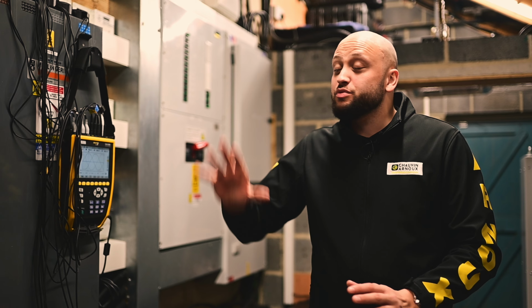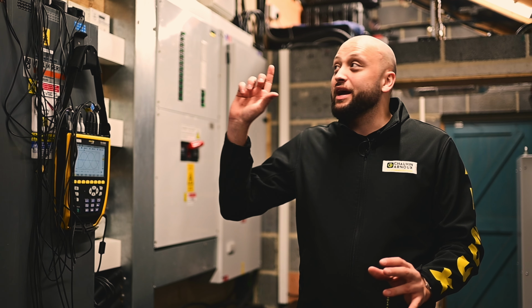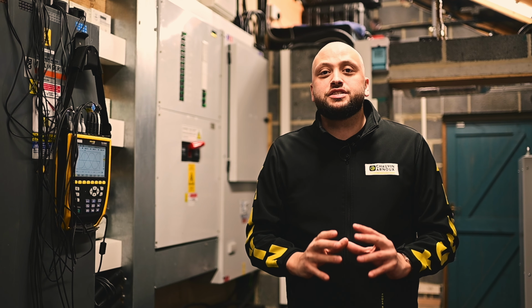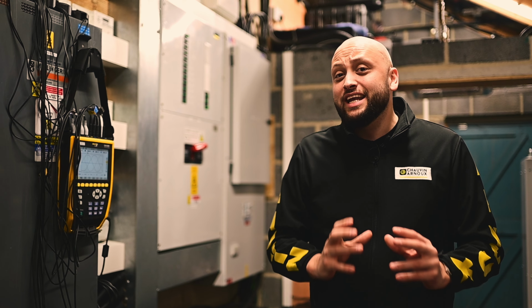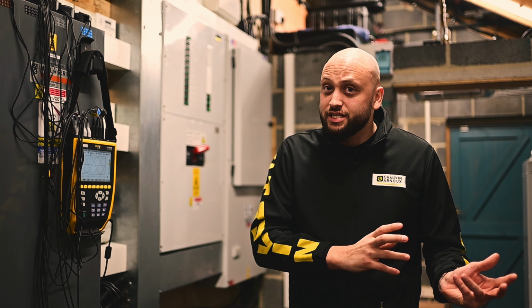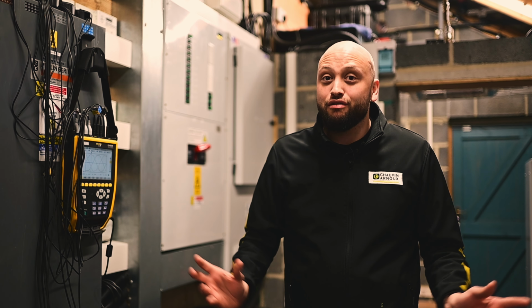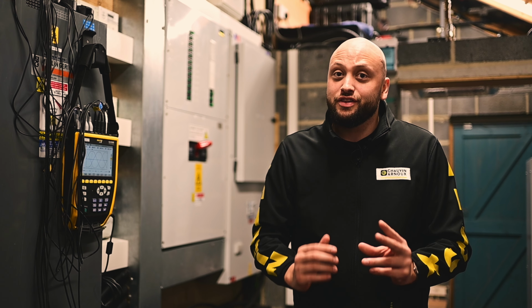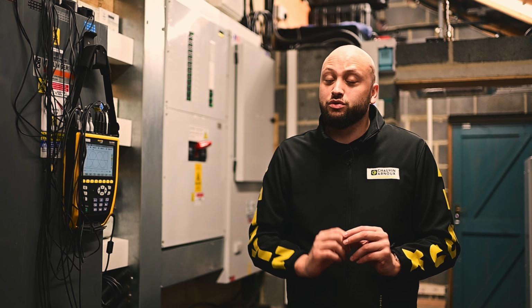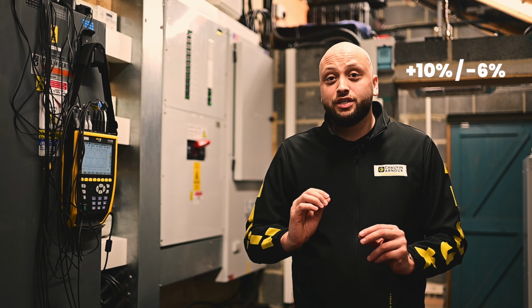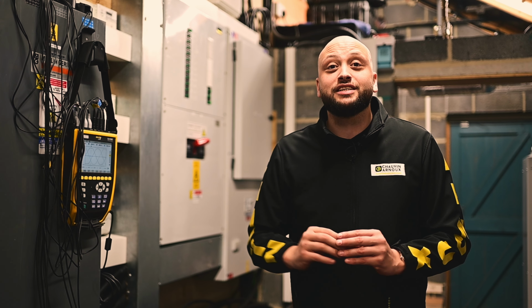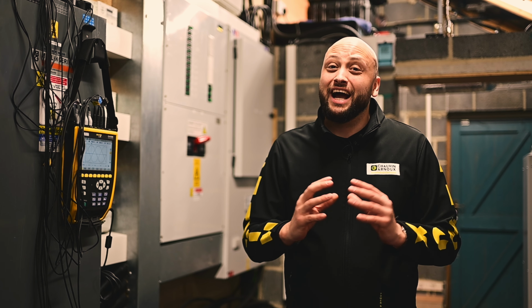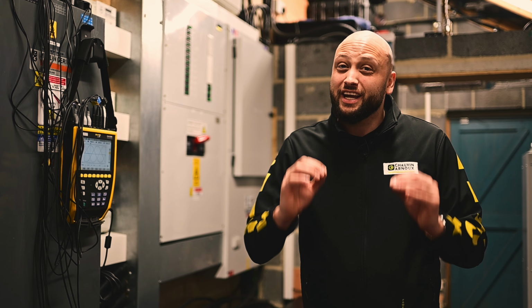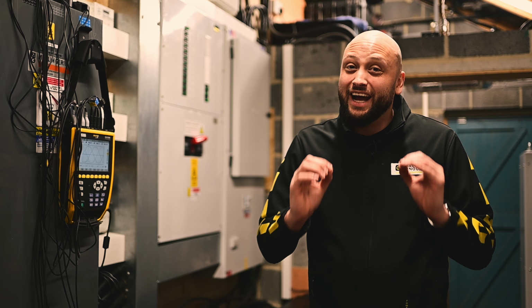Now we're going to install an 8345 on the main incomer supply. We're doing this to capture and see if there are any issues from a DNO's perspective, and also with the site's generation, to see if the voltage is going under the ESQCR limit of 230 volts plus 10 or minus 6. We're also checking that all the generation is operating as it should be, and we want to double check that it's operating as intended.